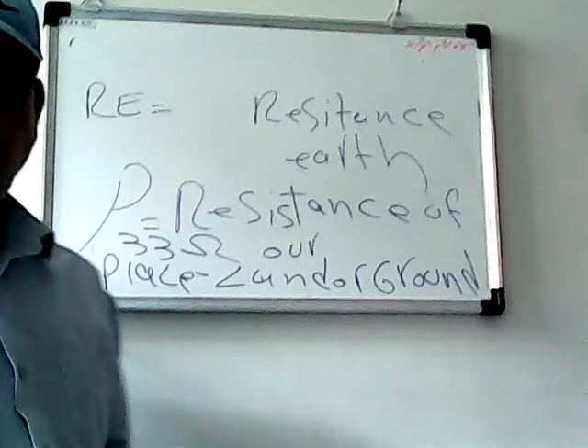A pipe electrode is used as a pit electrode, like a copper electrode - we use the pipe electrode. We just put it with a hammer - we weigh the end of the pipe, and put it with a hammer and dig it into the ground, into the land. This pipe is 2 meters long.